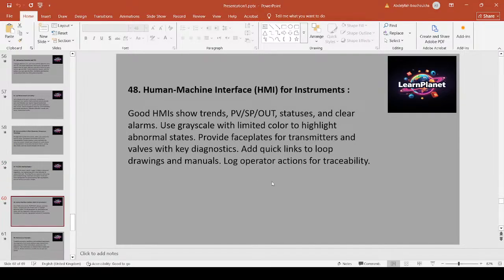HMI, Human Machine Interface for instruments. Good HMIs show trends, PV, SP, output, statuses, and clear alarms. Use grayscale with limited color to highlight abnormal states. Provide faceplates for transmitters and valves with diagnostics. Add quick links to loop drawings and manuals. Log operator actions for traceability.